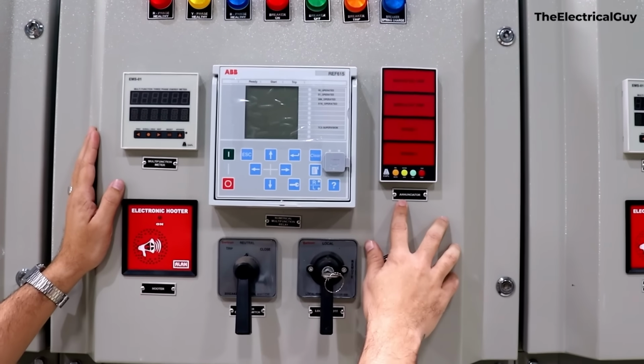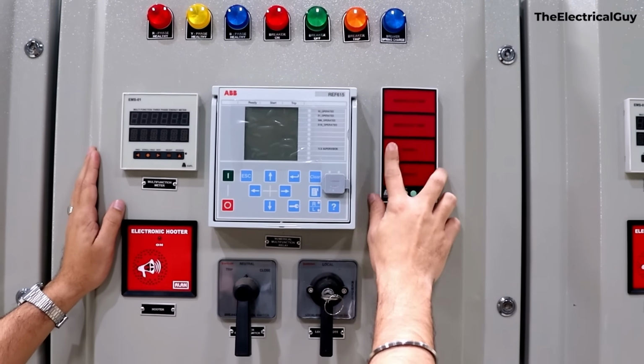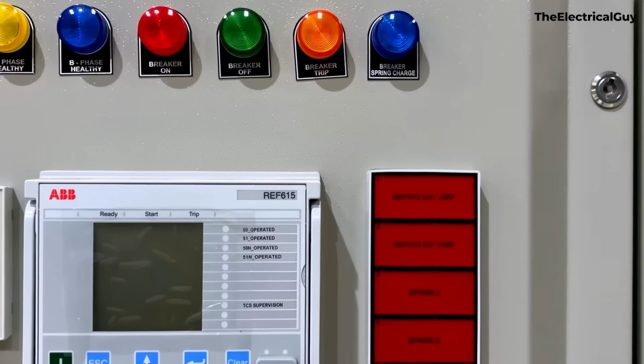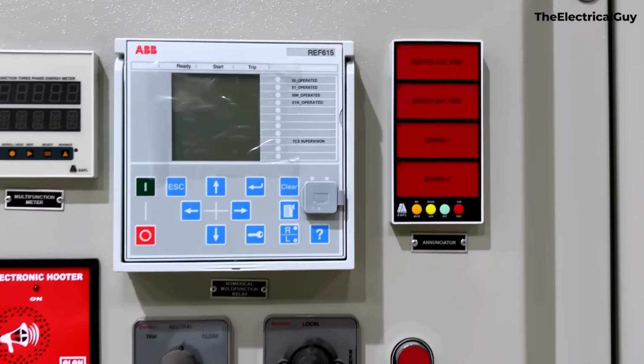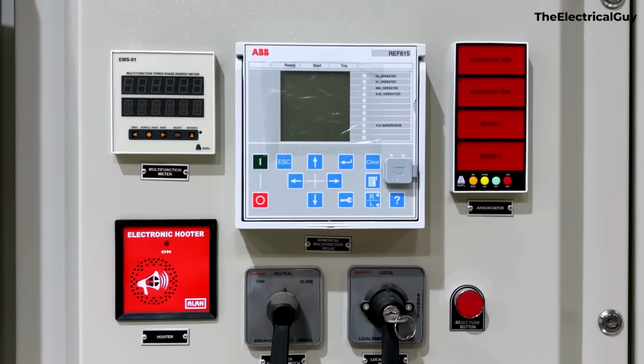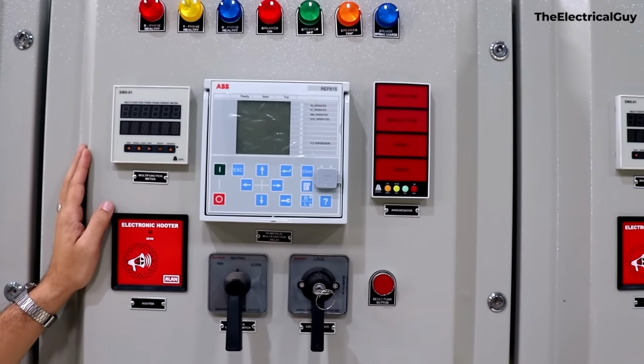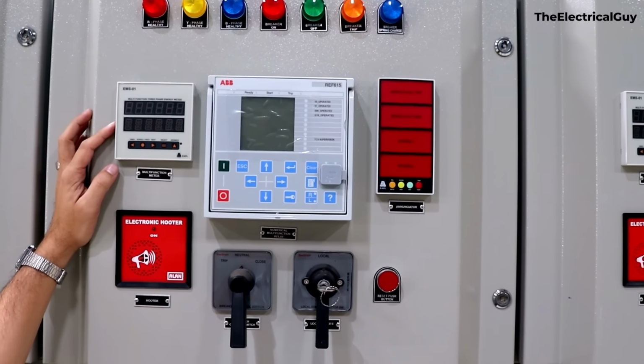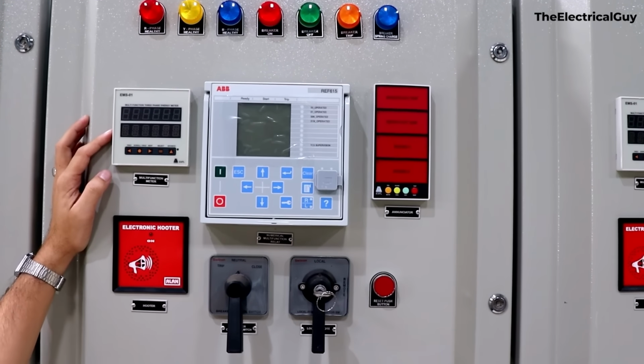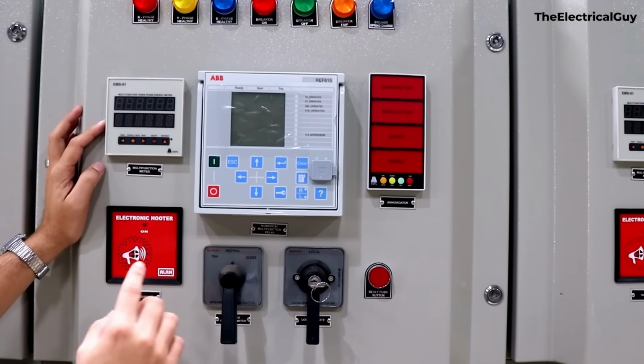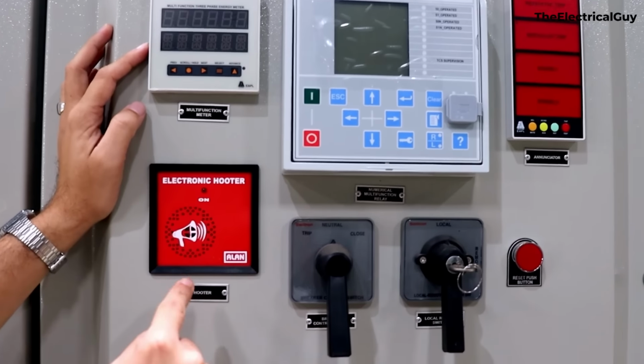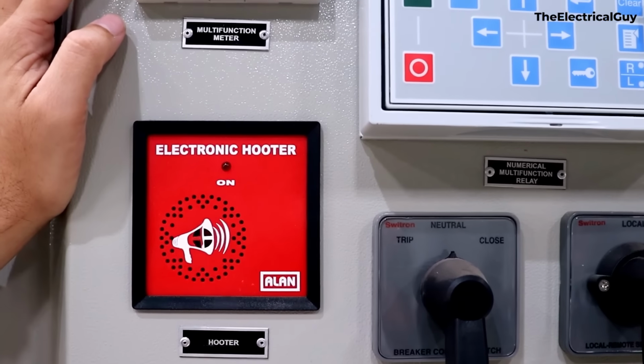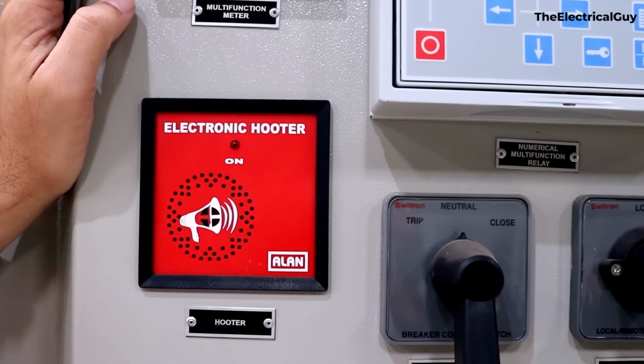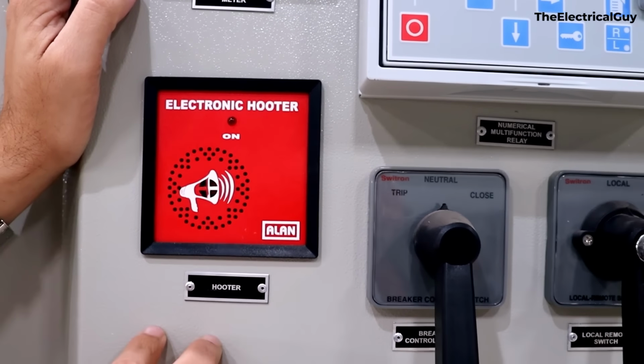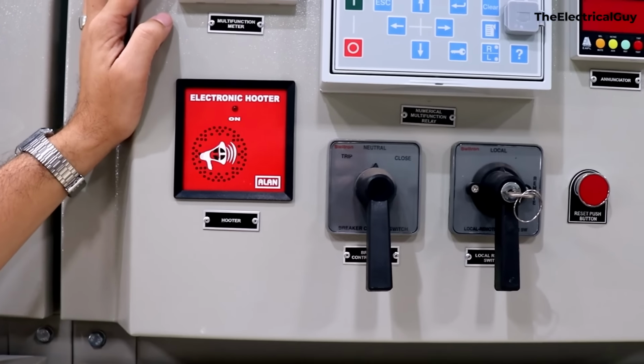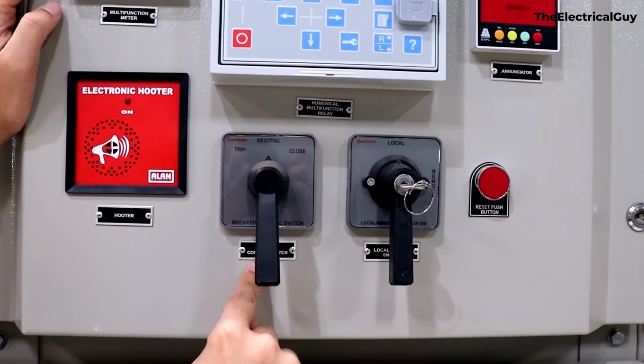And then we have the annunciator here. You can see the different indications are marked. So overcurrent trip, if that happens, you'll get the indication. This is earth fault trip, you'll get this indication. And then we have 2 spare items provided. So in case you want to configure it for some other things, you can do it on your own. And then importantly, we also have a hooter here, which will make noise when something goes wrong with this particular panel. Like this, we'll have hooters for every panel so that we know which panel is faulty, which panel is tripped.